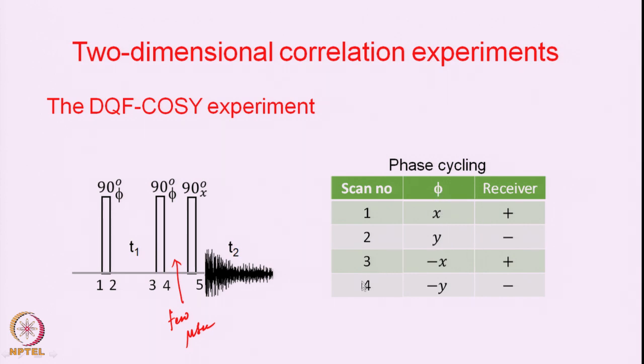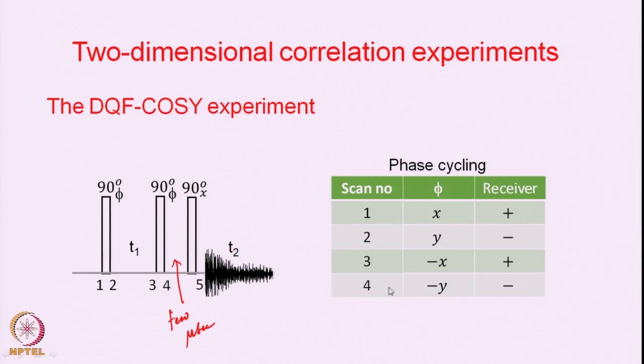You can have multiples of 4 scans — if you want 8 scans to improve signal-to-noise, you repeat the 4-scan cycle once more: scans 1–4 with this phase set, then scans 5–8 again with the same phase set. You can collect data in blocks of 4: 4 scans, 8 scans, 12 scans, 16 scans, and so forth depending on how much signal averaging you want to do.